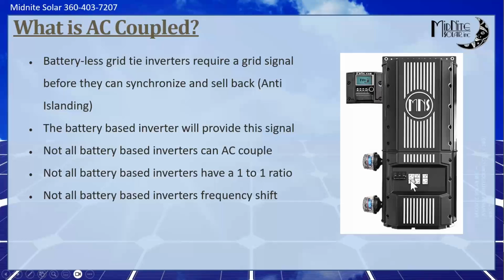And we have what we call a Z-wire that interlocks the two breakers and gives you a mechanical bypass in the E-panel. So if the Rosie was to ever fail for any reason, you can flip that bypass, shut the AC input breaker off, turn your battery breaker off, and the Rosie is completely out of the question, and everything is just back to running off the grid. So all of our Rosie E-panels accommodate a bypass. The P100 has a 120 amp bypass for dual Rosies. If you were going to stack, say, 4 Rosies, then we would need to do external switchgear.